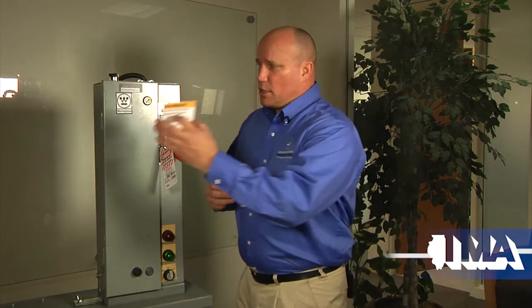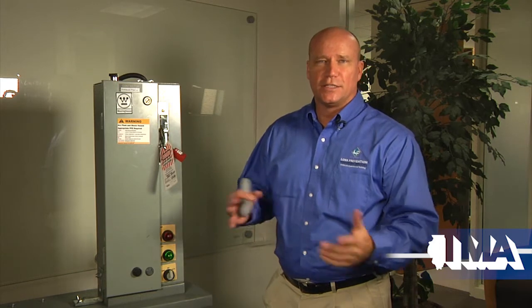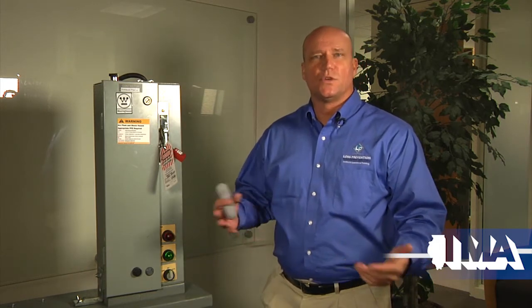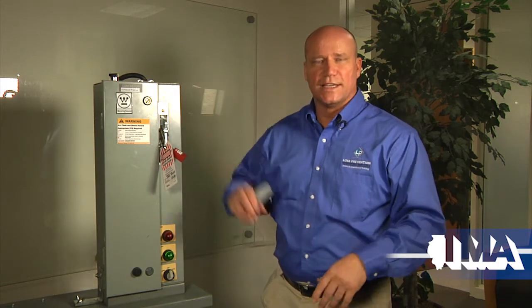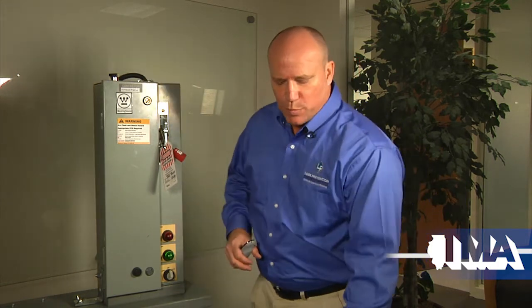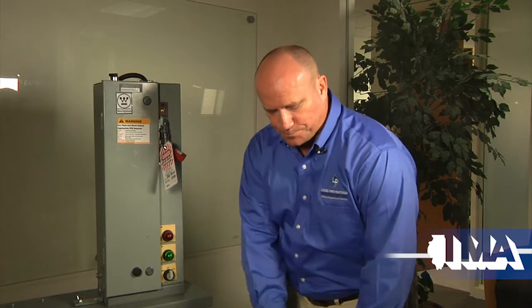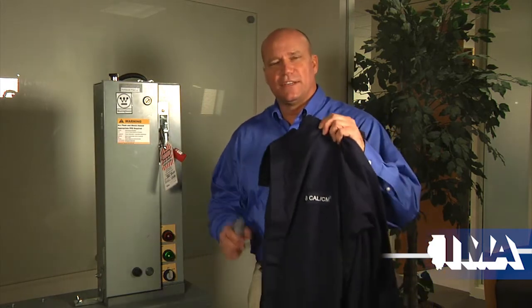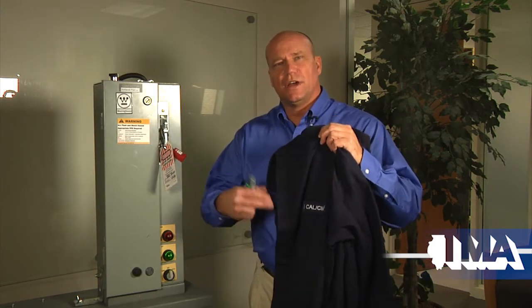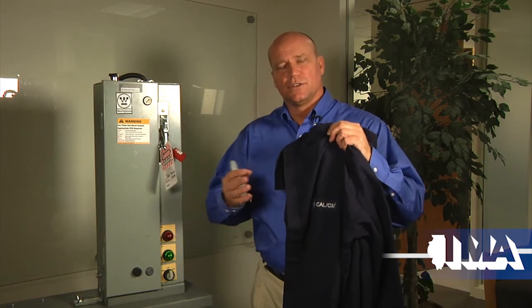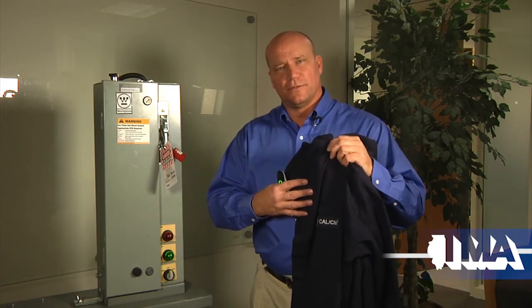So if you were looking at a label, and labels were installed like you have here, to get the important information that you need to know, the cals per centimeter squared. Now that's based on the worst case, 3-phase short across all 3 phases in the worst case condition. So I can select my personal protective equipment based on that. For example, that was 1.7 cals. An 8 cal suit is greater than 1.7, so this suit will be able to protect me from the thermal energies involved with an arc blast.